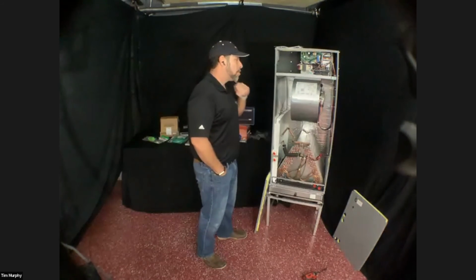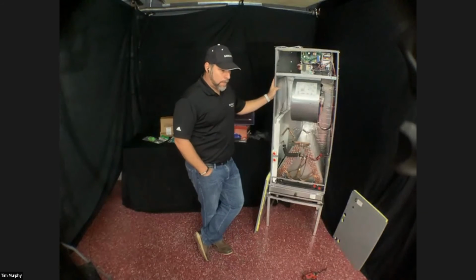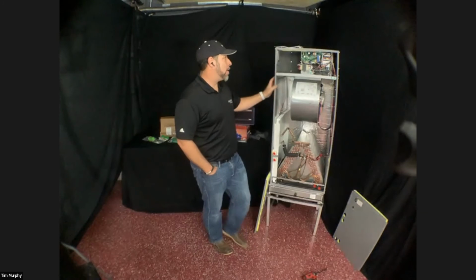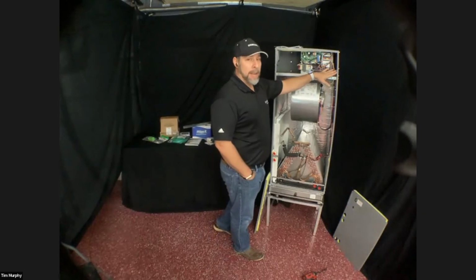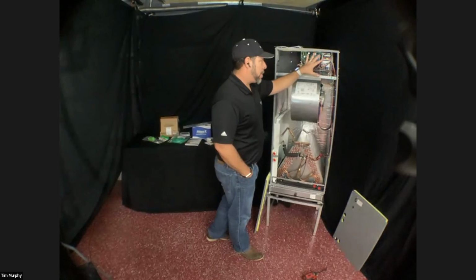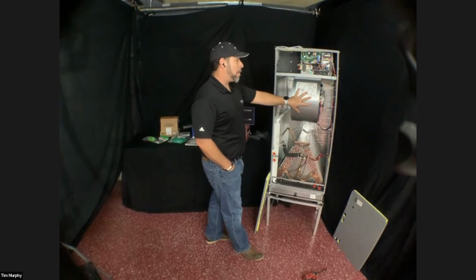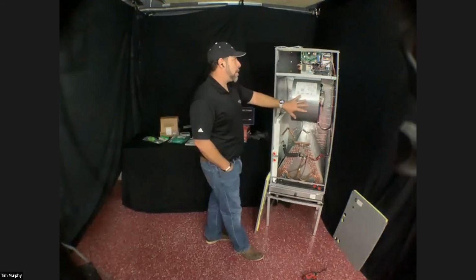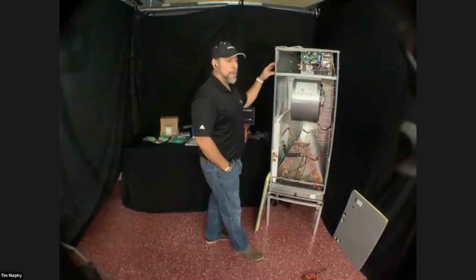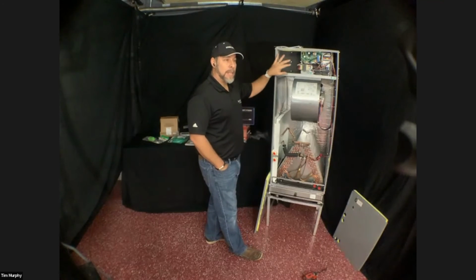Dave Abel has a follow-up question on the heat kit - the high voltage, will it have dedicated wire, or use the old wire? Yes, so you're going to power the air handler off the condenser. That's going to power up the board, power up the evaporator fan motor, and supply necessary power for that. Then you will have to run an additional line voltage for the heat kit.